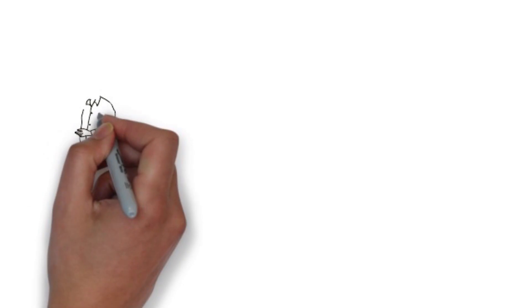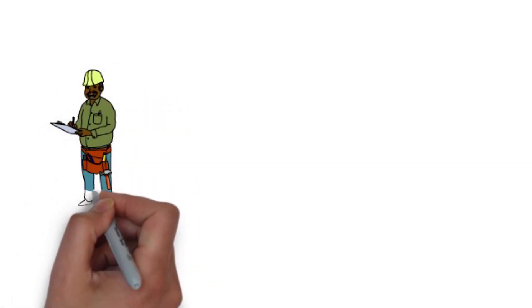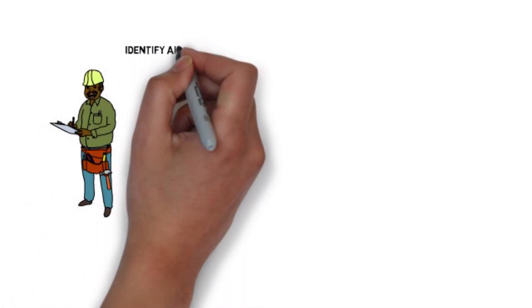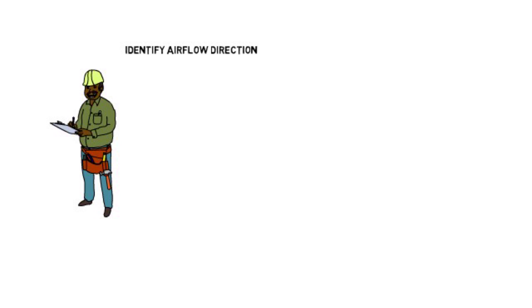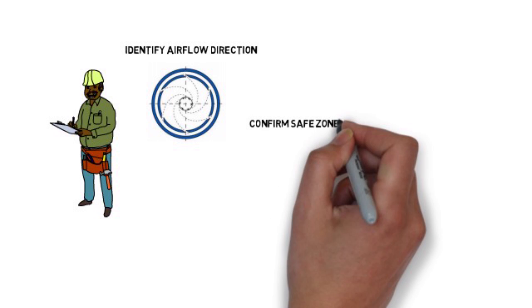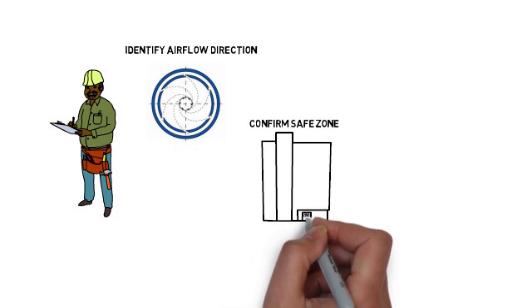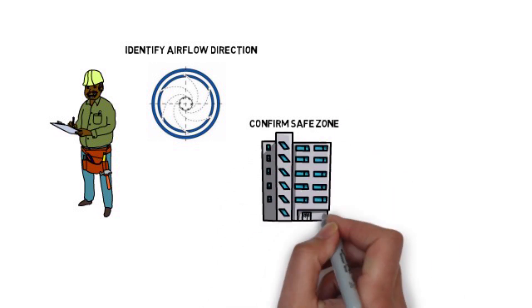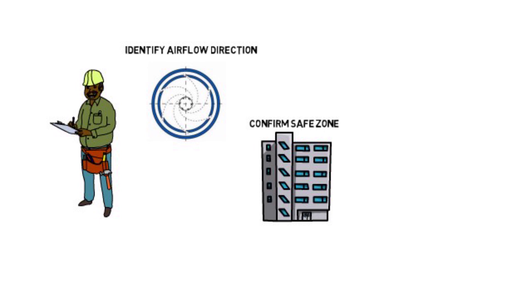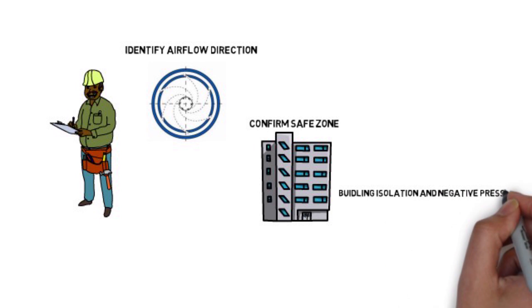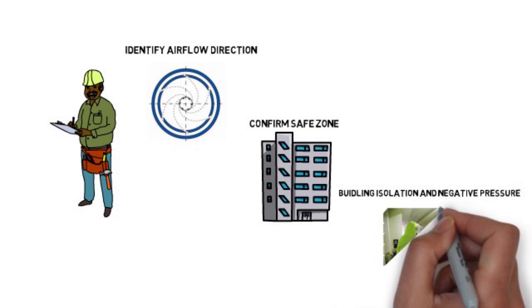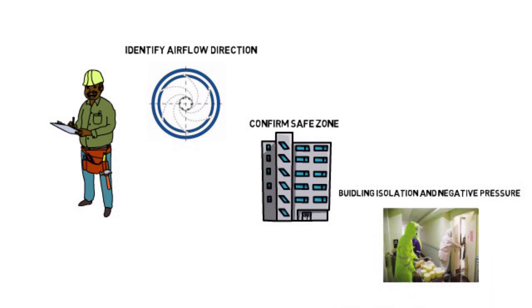How can engineers help in emergency planning? First, you can identify vulnerabilities with air intake and airflow direction to make sure they are designed properly. Next is to confirm the building is in a safe zone. For designated shelter-in-place locations in a building, identify approaches to interrupting air supply and guarantee these locations are absolutely safe. Finally, identify cohorting possibilities for pandemic situations so that whole areas of a hospital may be placed under isolation and negative pressure.